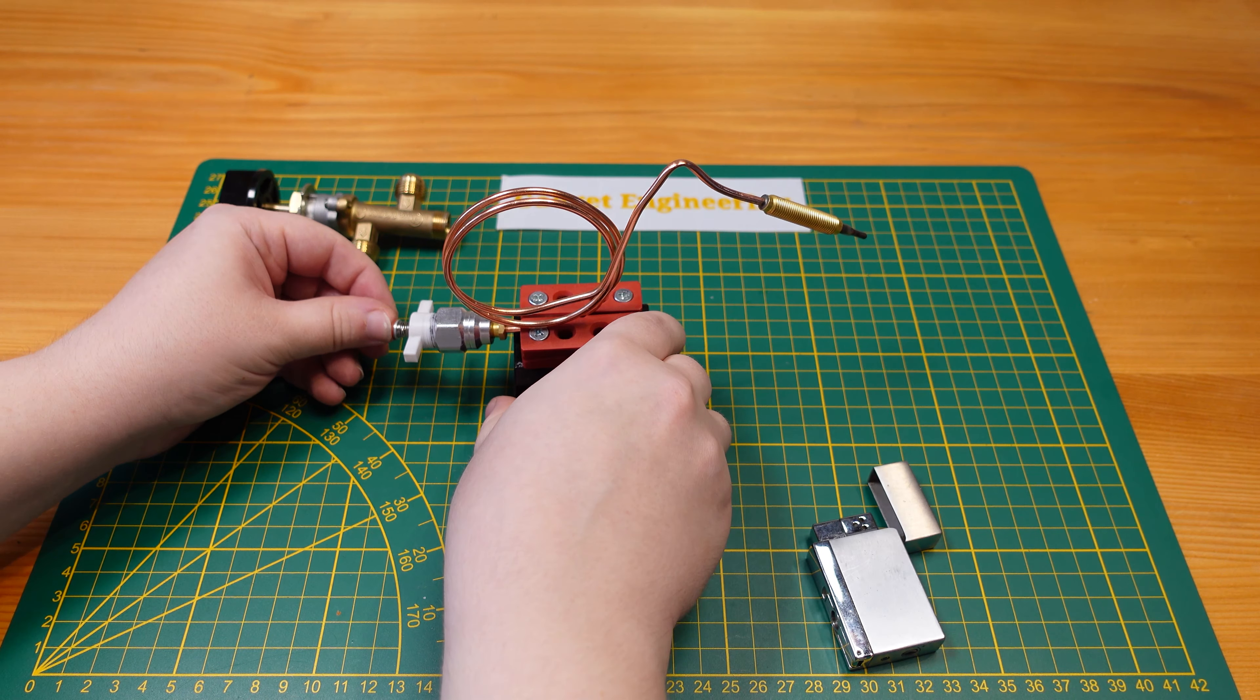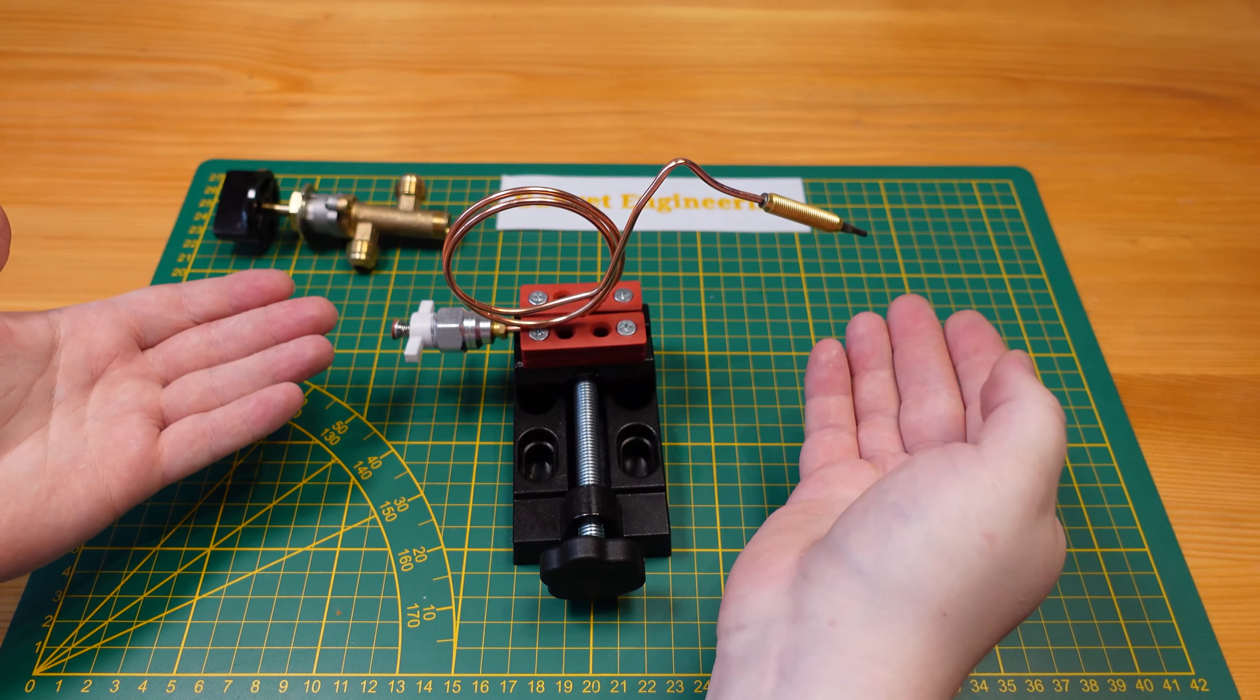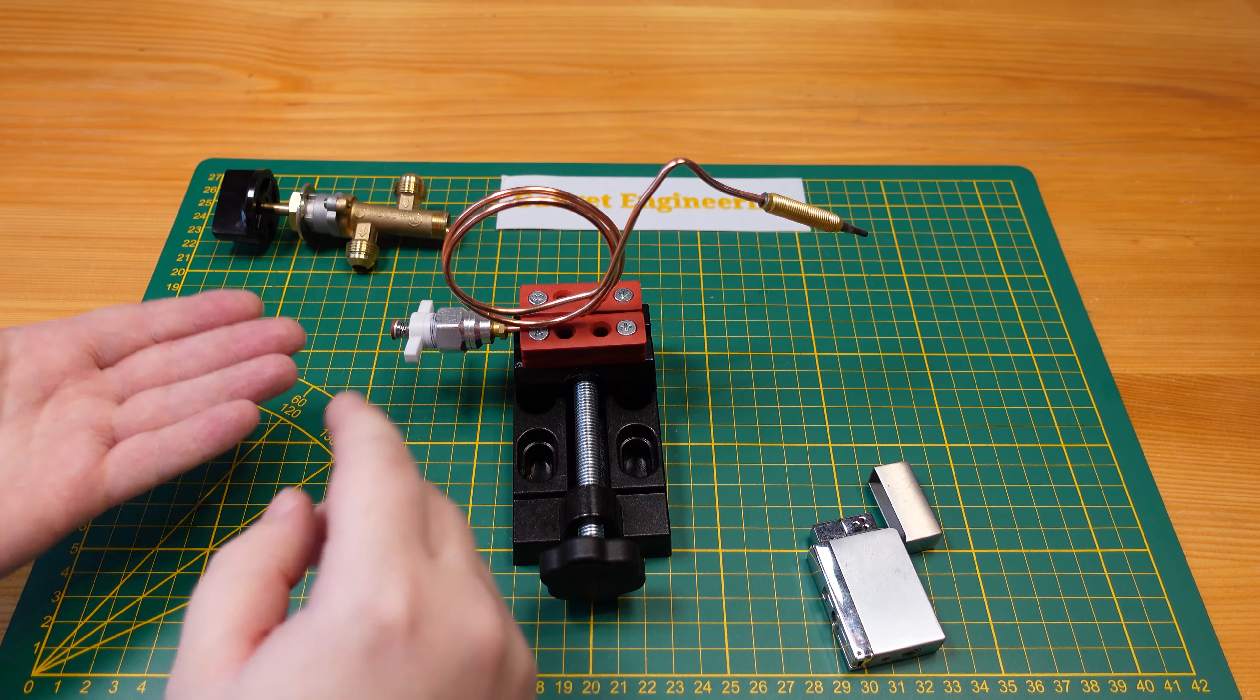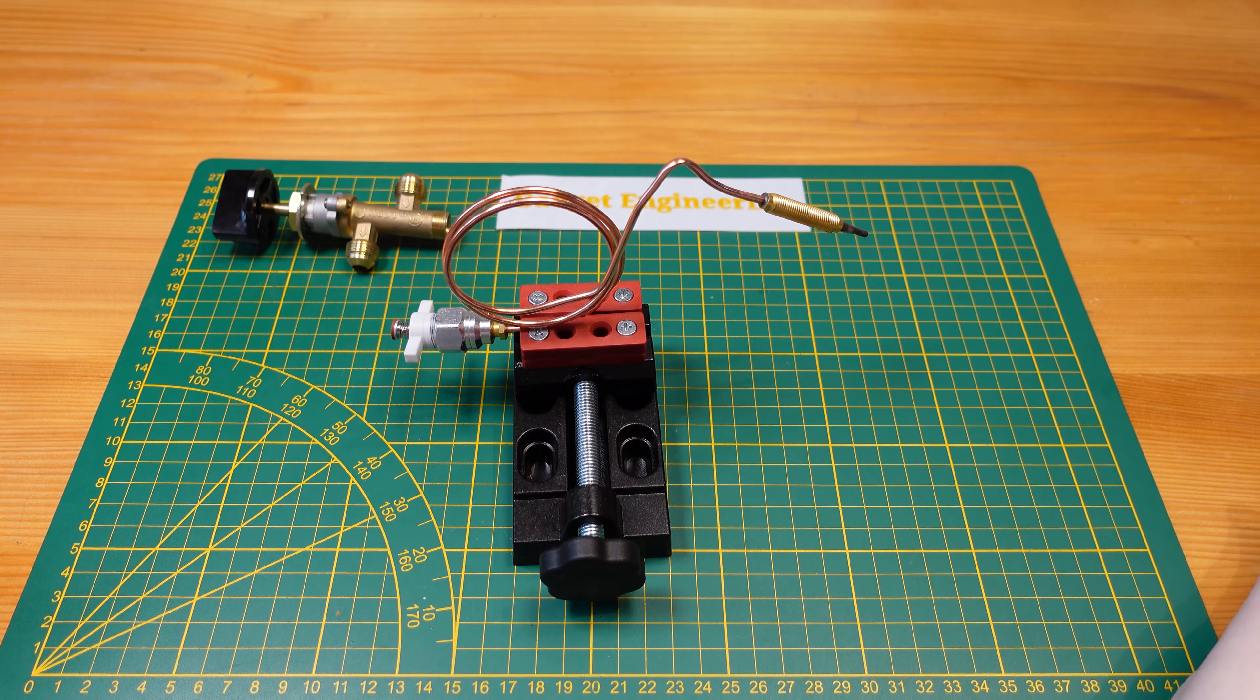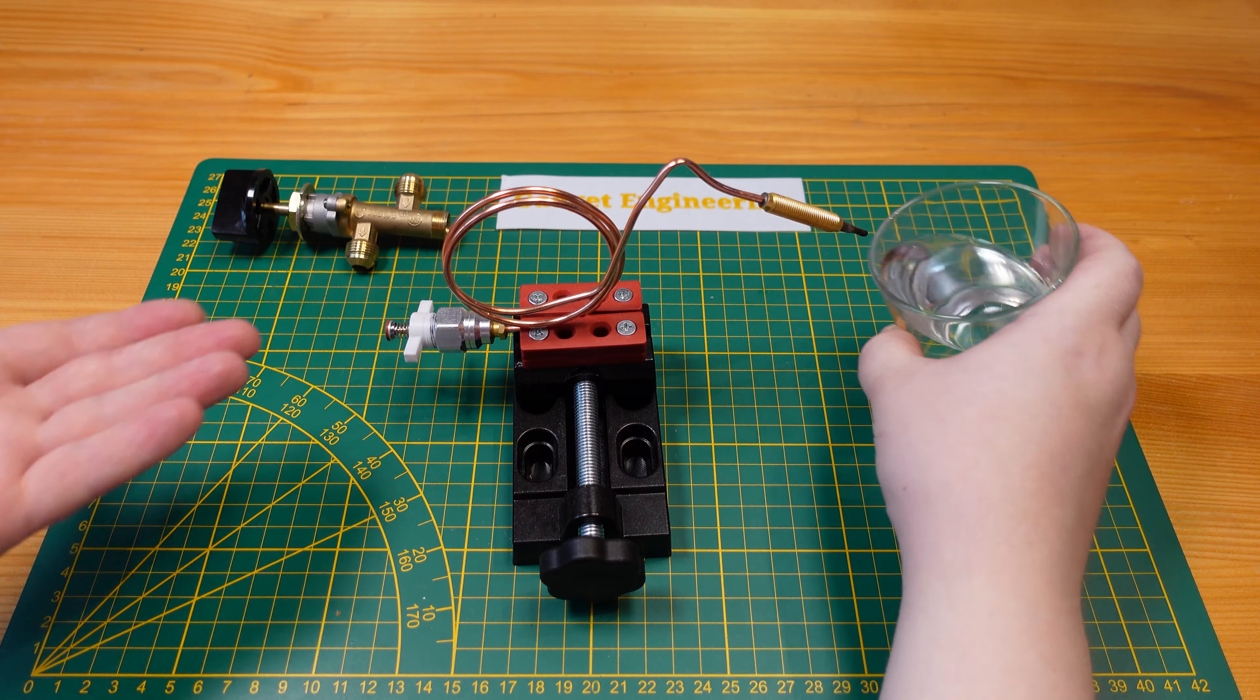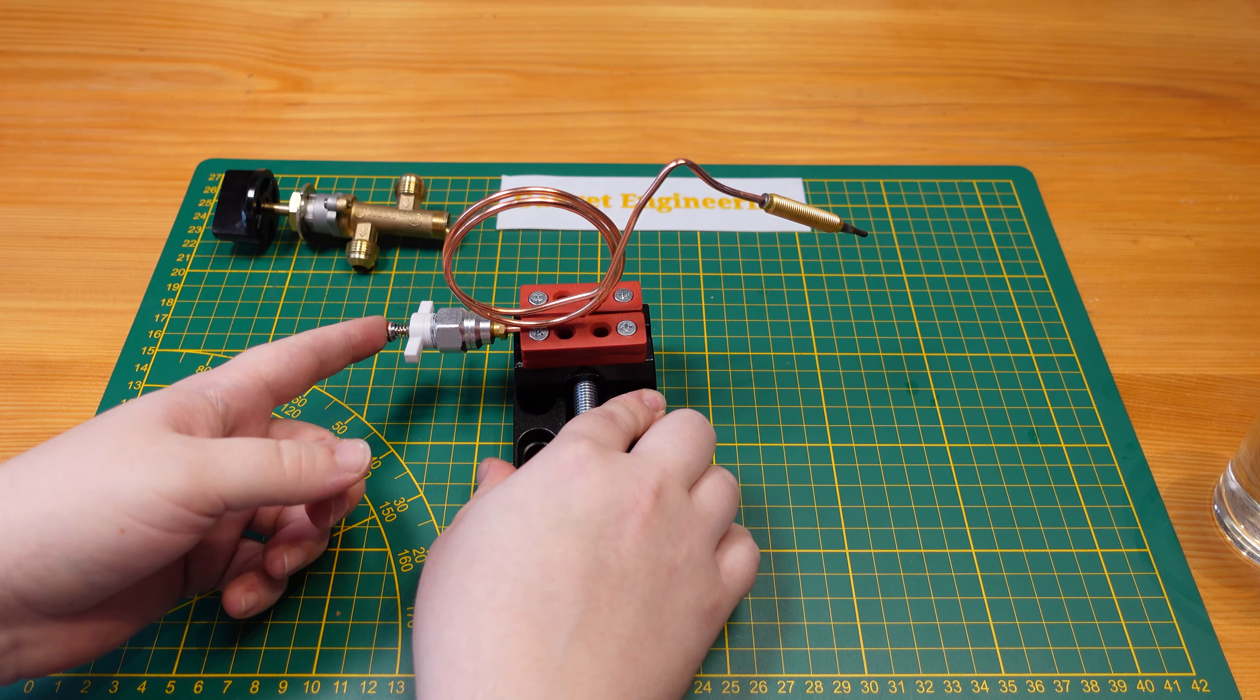So even if I sort of jiggle this a little bit, the electrical current that is being produced by the thermoelectric effect is holding against the spring pressure and is holding the valve open. So let's say this is now the burner has been blown out. It's not heating anymore. There is obviously a little bit of a thermal delay, but when we cool the thermocouple, it pops out the valve and stops gas flow.